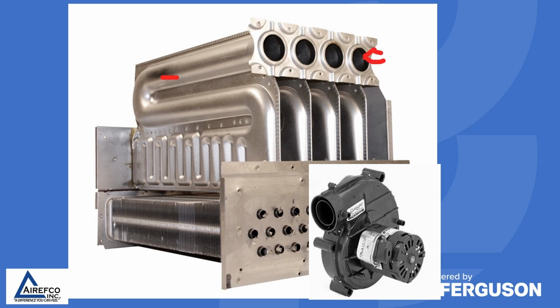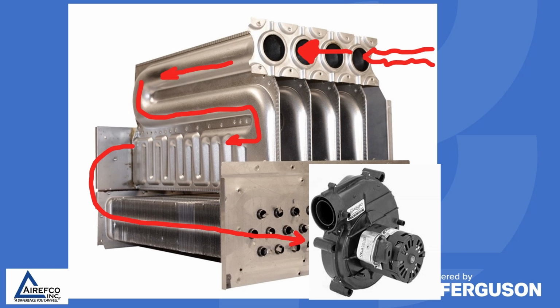Number one, when the flame is established in the primary heat exchanger, the inducer motor draws the flame and the products of combustion into the primary heat exchanger and directs them through the channels of the heat exchanger. When it exits the primary heat exchanger, the inducer motor then draws it through the secondary heat exchanger, where more heat is extracted from the products of combustion. Then the inducer motor exits the flue gases out through the vent.